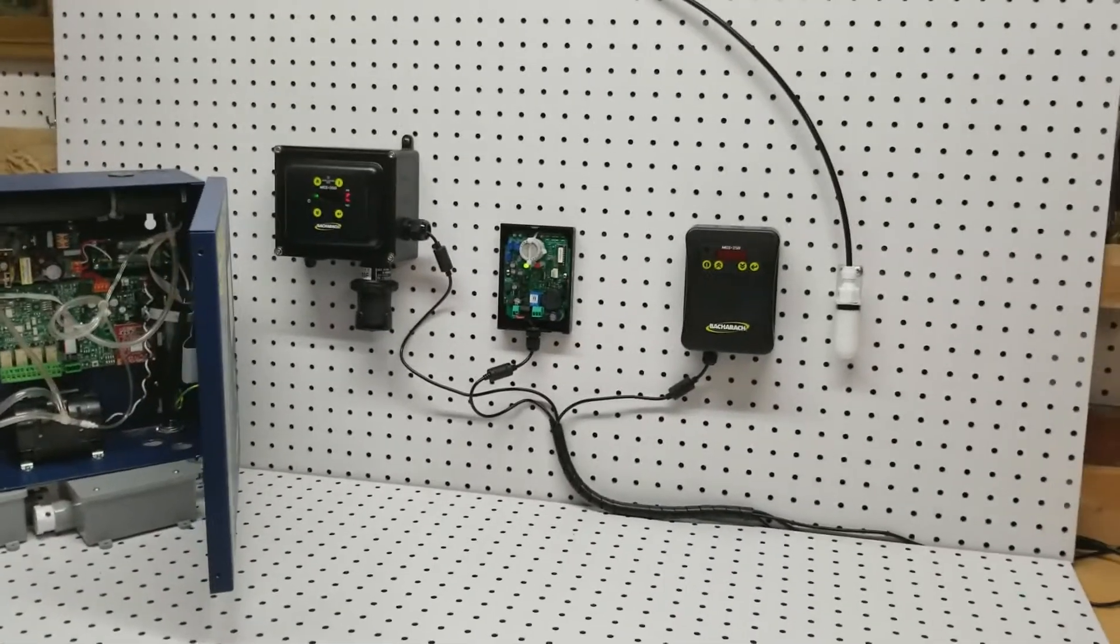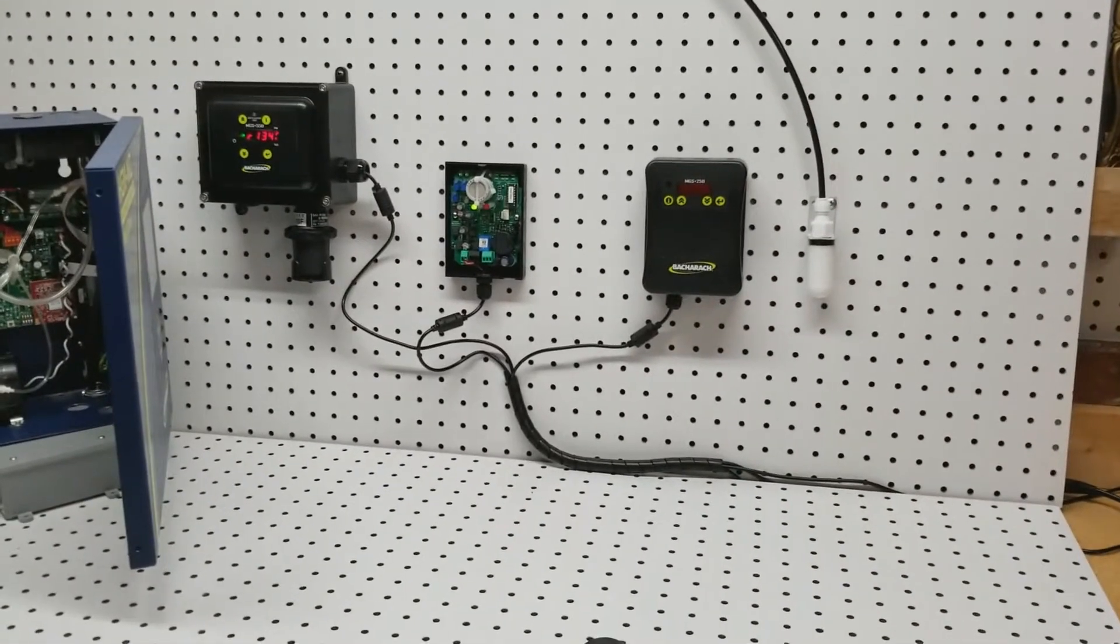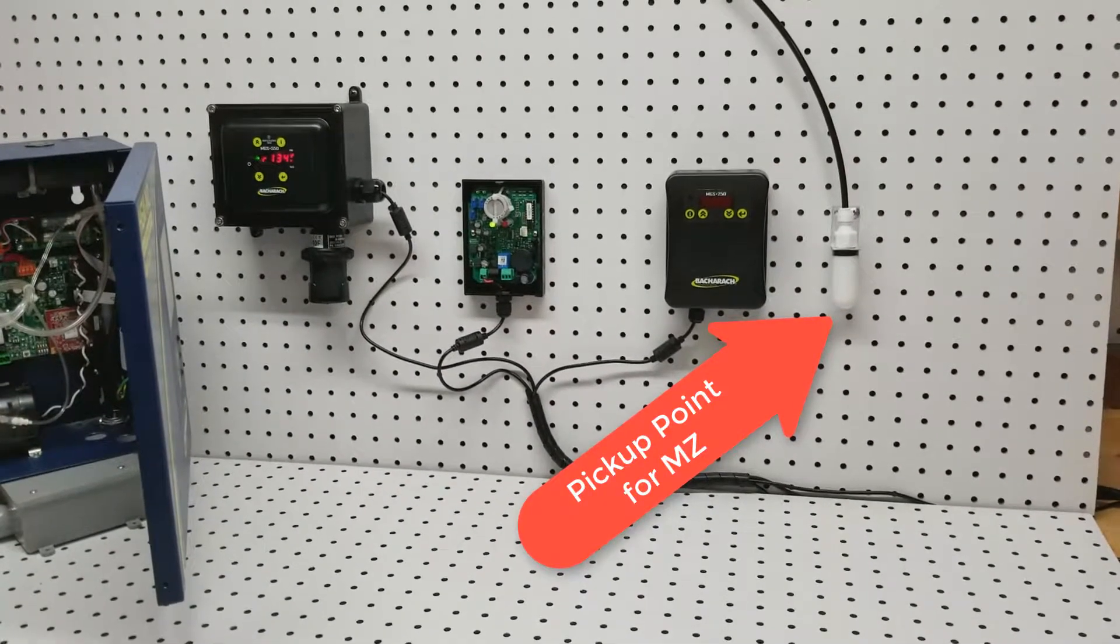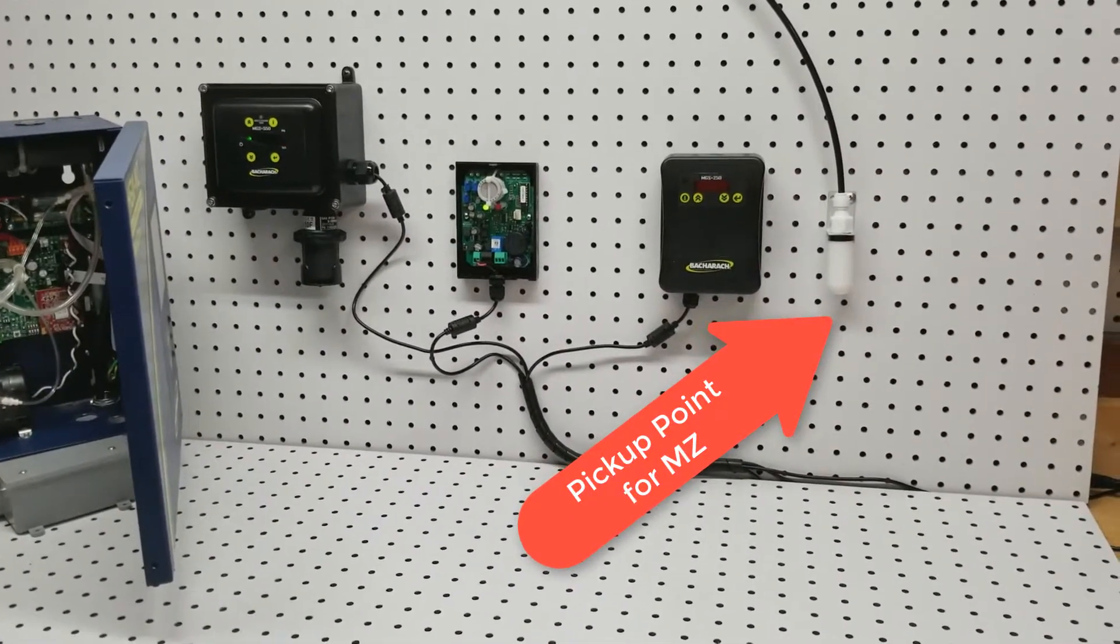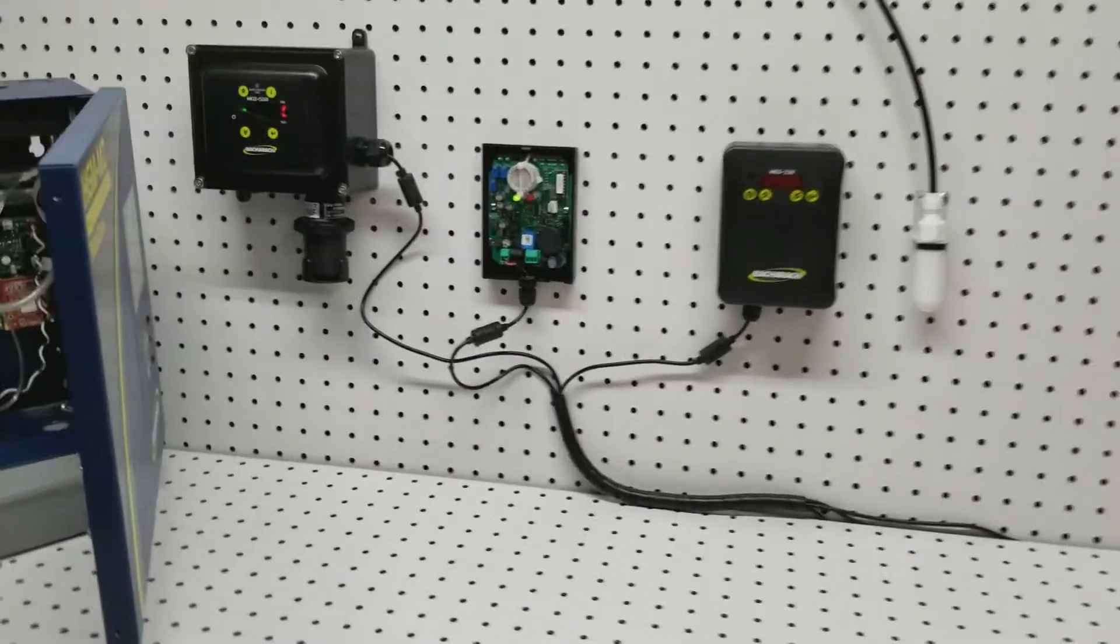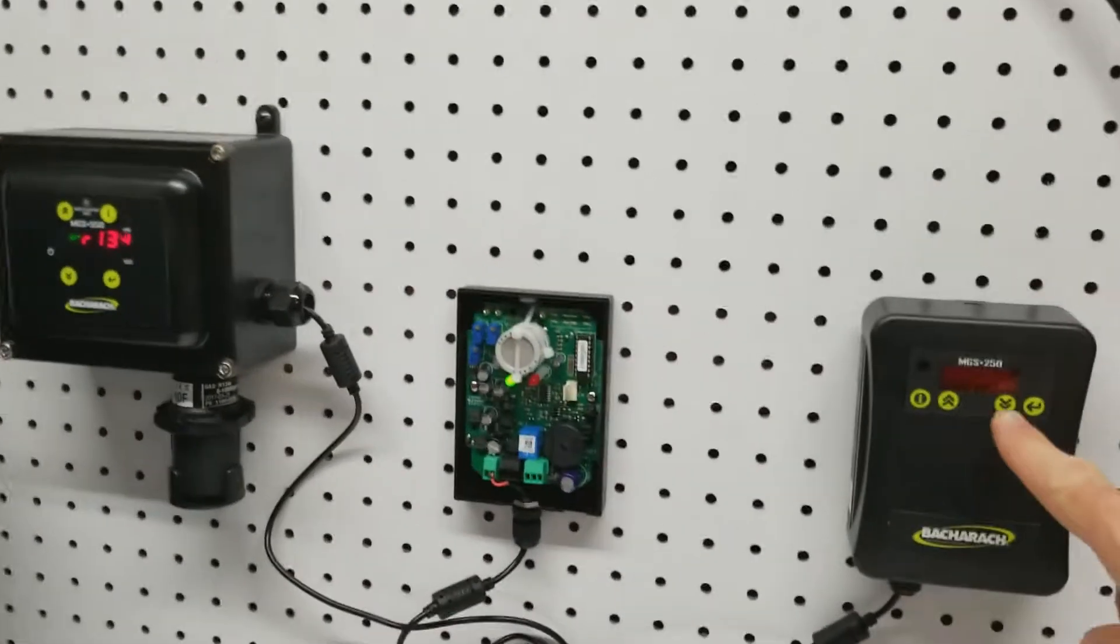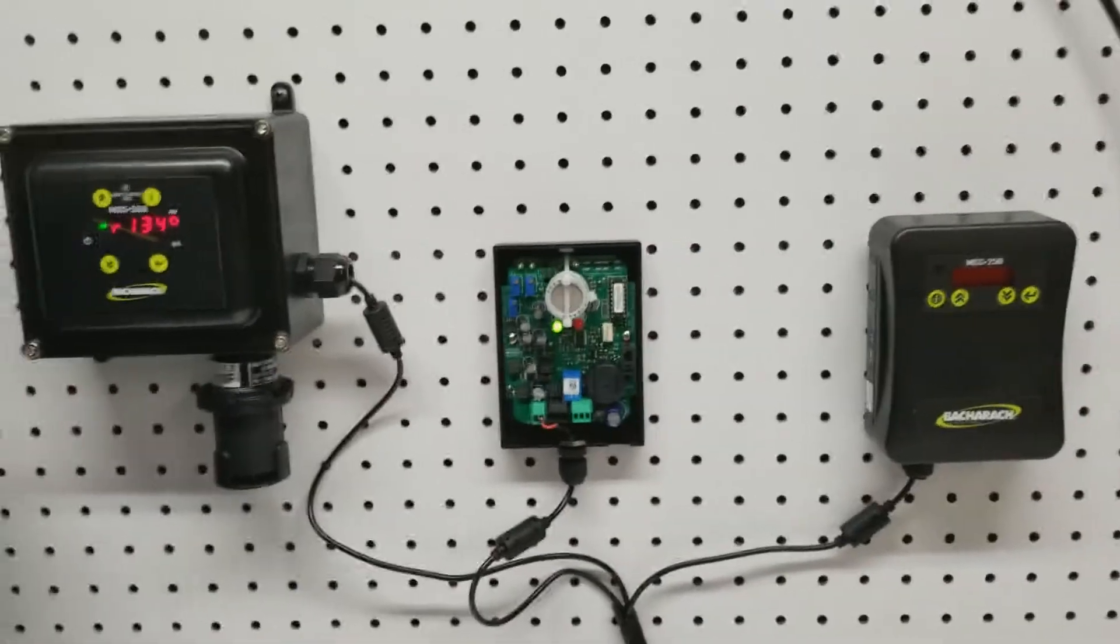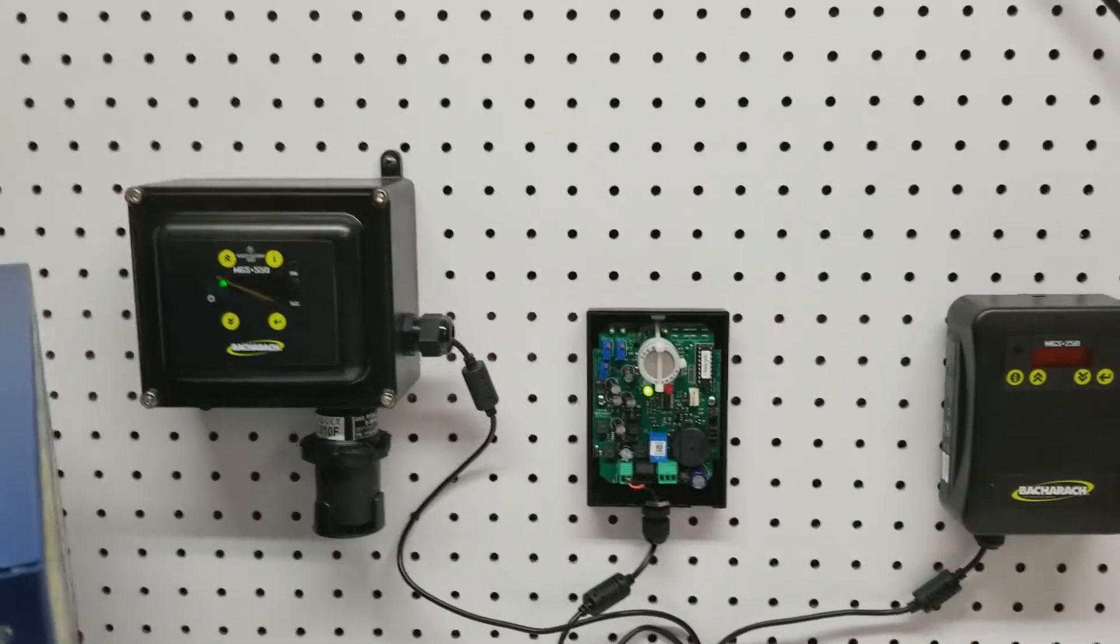I have these units all set up at the same level. The manual says between 6 and 18 inches, and in this case, I would imagine a lot of these ones that have the readouts are probably going to be placed at eye level, which is really not where they should be. They should be low.